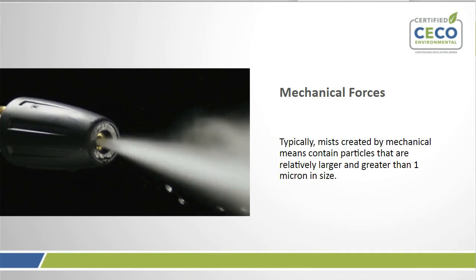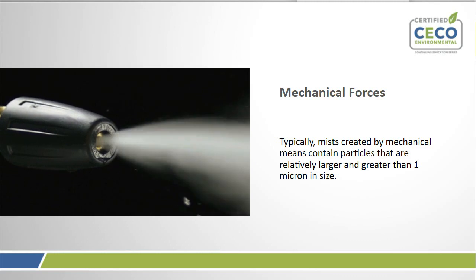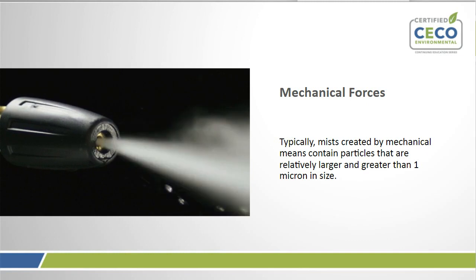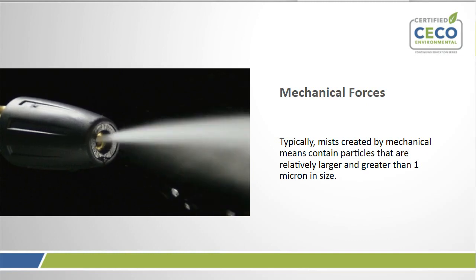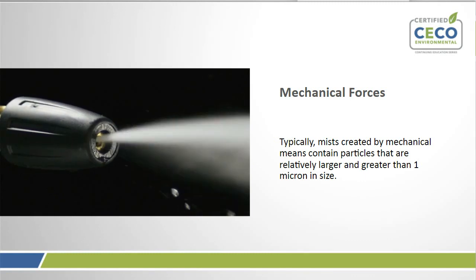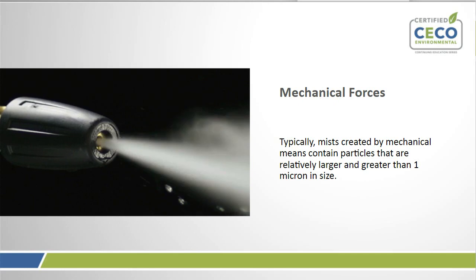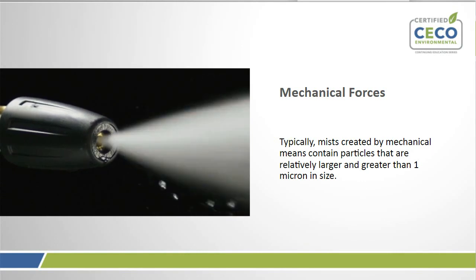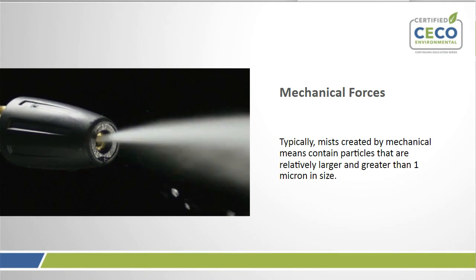Droplets can also occur from bubbles bursting or jetting at a gas-liquid interface, typically in distillation columns, evaporators, bubble columns, and flooded packed bed scrubbers. These droplets become entrained in the upper gas flow, and if not abated, will cause downstream equipment corrosion and air pollution. The mist mean size in mechanical formation is equal to or greater than 2.5 microns in size.